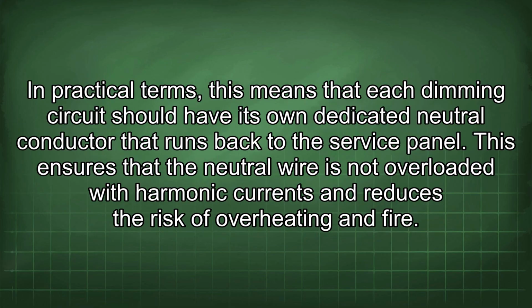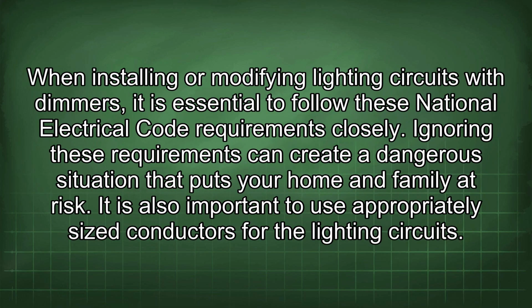In practical terms, this means that each dimming circuit should have its own dedicated neutral conductor that runs back to the service panel. This ensures that the neutral wire is not overloaded with harmonic currents and reduces the risk of overheating and fire. When installing or modifying lighting circuits with dimmers, it is essential to follow these National Electrical Code requirements closely. Ignoring these requirements can create a dangerous situation that puts your home and family at risk.